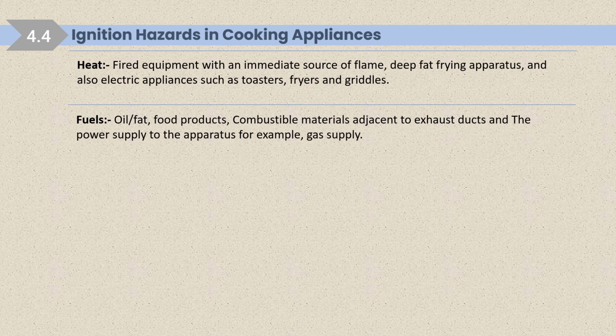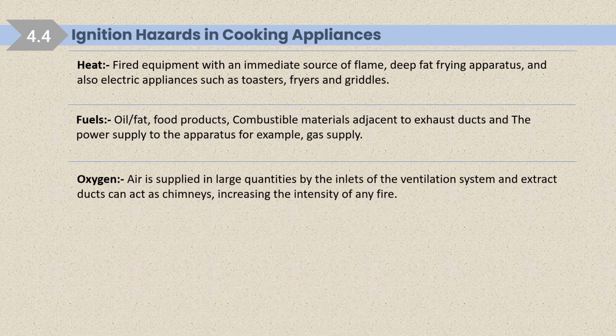Fuels. So what are the fuels there? Oil, fat, food products, combustible material adjacent to the exhaust duct, and the power supply to the apparatus, for example gas supply. Oxygen: air is supplied in large quantity by the inlet of the ventilation system, and extract ducts can act as a chimney, increasing the intensity of any fire. So this is the ignition hazard in cooking appliances.